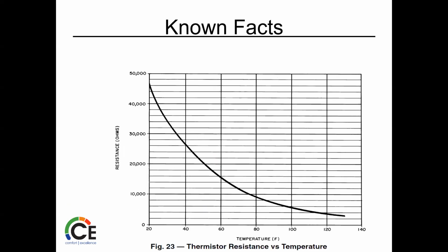Thermistor resistance: the colder it is, the higher the resistance is. So they're an NTC resistor, just like a lot of the residential units out there. So again, you're looking at that chart. If it's 40 degrees when you're testing it, you should see, what's that, 28 to 30,000 ohms.